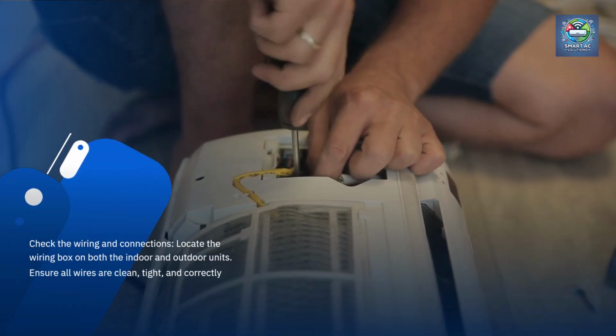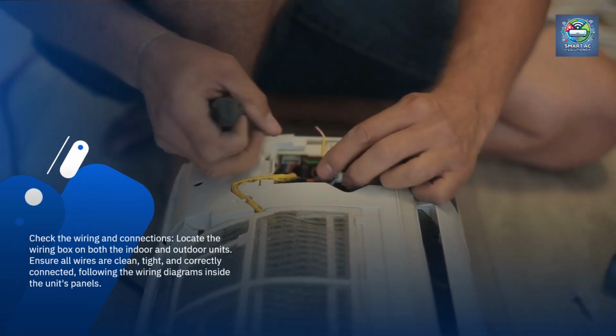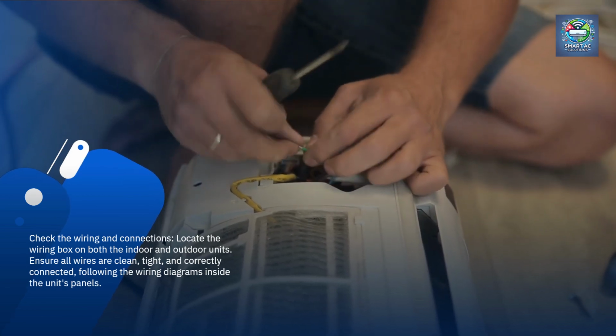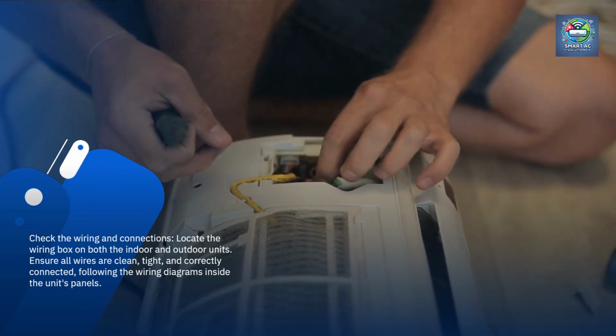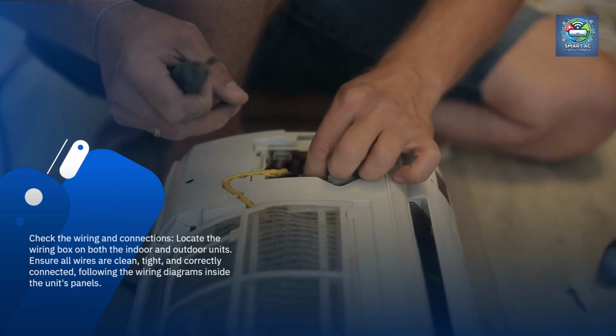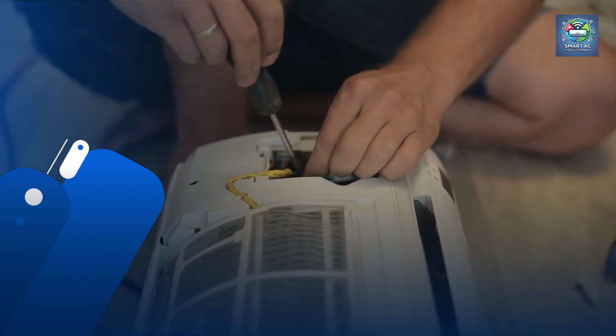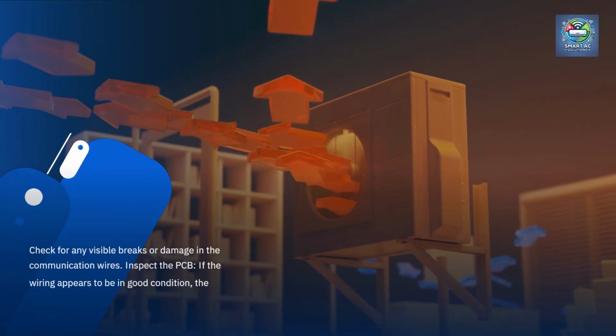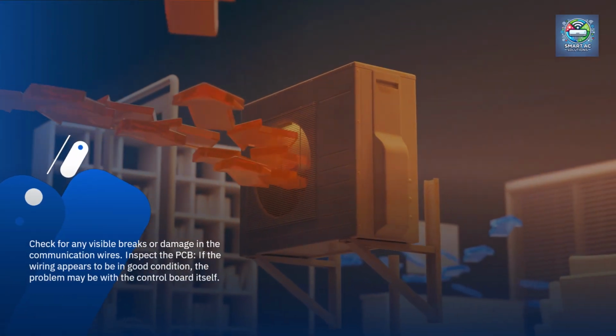Check the wiring and connections. Locate the wiring box on both the indoor and outdoor units. Ensure all wires are clean, tight, and correctly connected, following the wiring diagrams inside the unit's panels. Check for any visible breaks or damage in the communication wires.